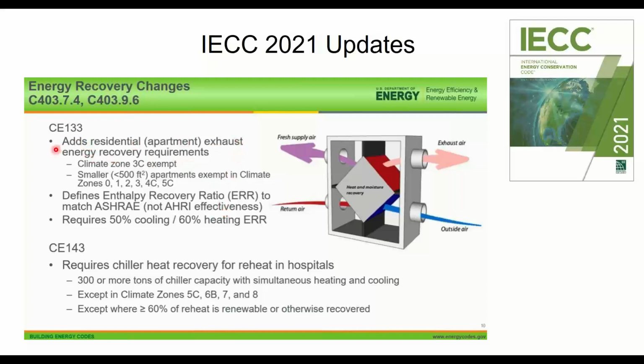So an apartment building complex will have to have energy recovery. You have all these little exhaust fans coming out—you'd be smart to combine them into one big centralized exhaust and run them through one big ERV, or you could do a bunch of little individual ones. That's fine too. But you're no longer going to have the exception to get out of doing it for an apartment building. Apartment buildings, by the way, fall under the commercial code unless they're 3 stories or less, or in some cases 4 stories or less in certain places like Chicago.